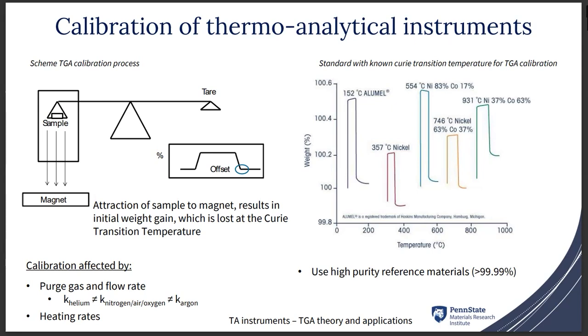What is important to know about calibration of those types of instruments is that the calibration is highly sensitive to the purge gas you use, because different gases have different thermal conductivity. So the thermal conductivity of helium is different from that of air, which is different from argon. It's dependent on flow rate, and it's dependent on heating rate. So while TGA or DSC are very important to understand the material, often they don't give a full picture of what's happening inside your material.